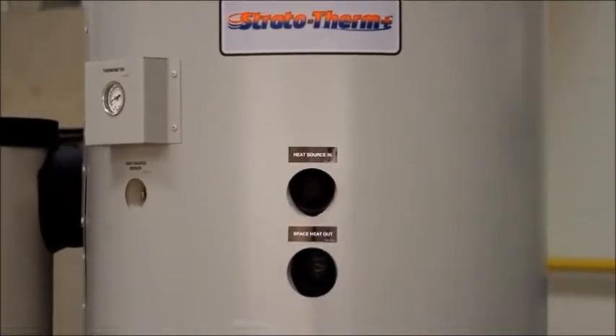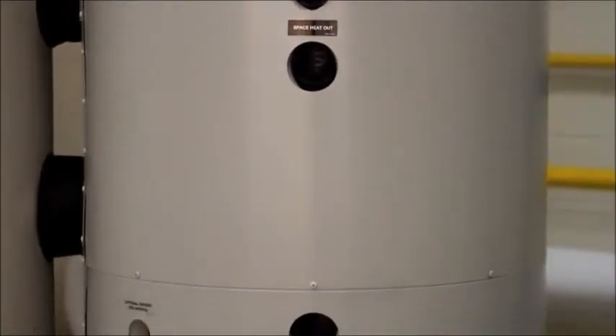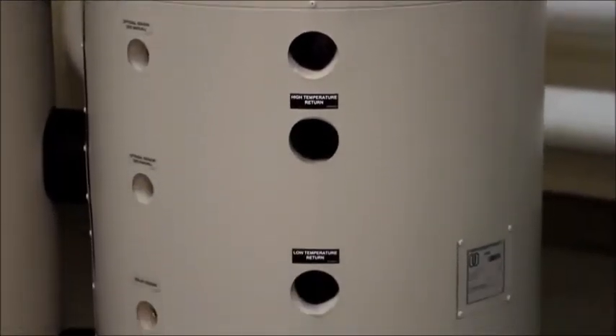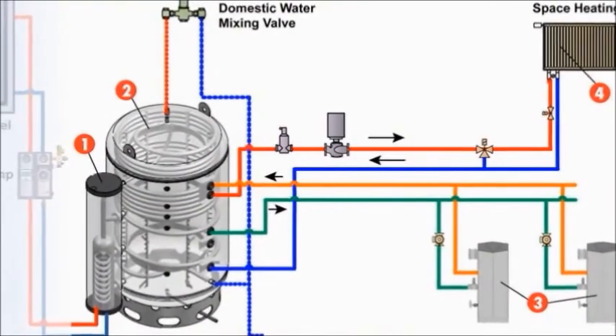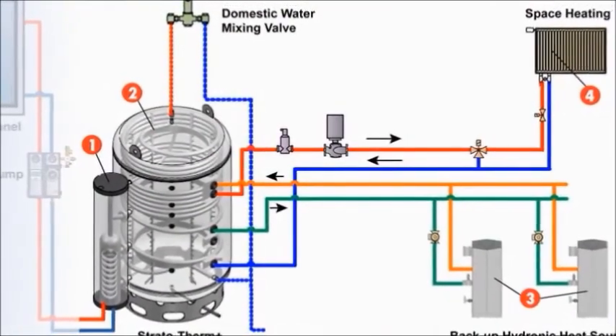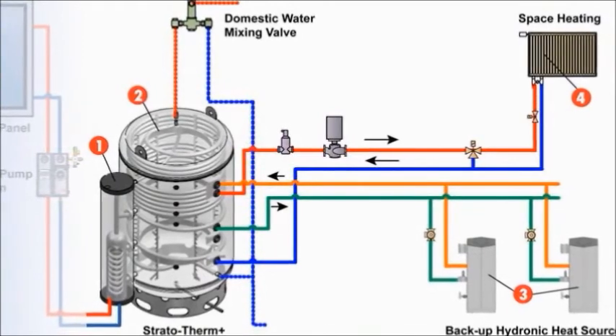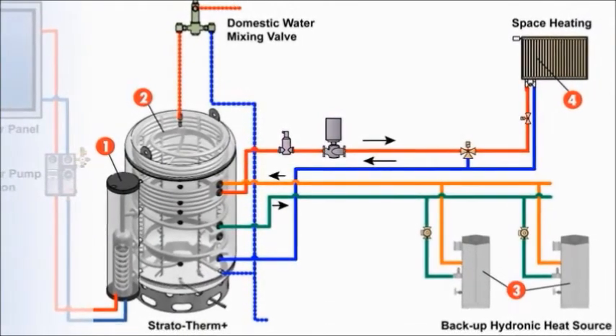Here we have boiler supply and return connections which allow decoupling of the boilers from the system demand. Additionally, we have designed the tank to accommodate multiple temperature systems by supplying heating water from near the top of the tank to ensure the space heating load is met, and keeping the tank stratified by returning lower temperature water to the bottom of the tank. The tank does a remarkable job of unifying solar and closed-loop hydronic systems, but there is a third component that we have not discussed, which handles domestic hot water production. Jeff, tell us more about that.